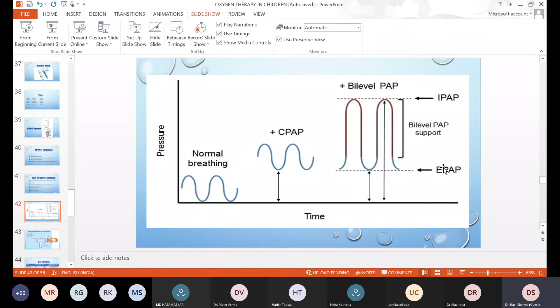Now the next system is bubble CPAP. This is the diagram showing what bubble CPAP is. As I have already told you, here we are providing a continuous positive airway pressure. This is the system. Here the oxygen and the air are blended. Then through the flow meter we set the flow, how much flow we want to give to the patient, and the gases come out of the flow meter. And this is the humidifier. Here the gases will be humidified and heated.